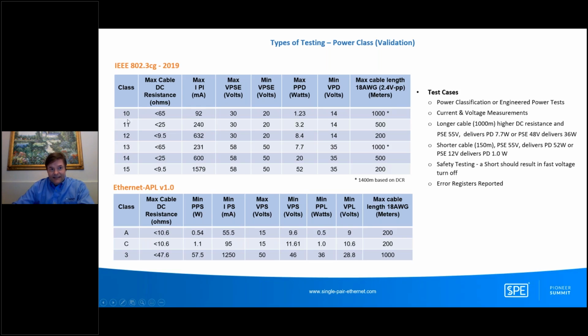But if we look at class 10 through 12 first, you'll see that the voltage power supply on the power source equipment is between 20 to 30 volts. So let's just say typically about 24 volts being supplied from the power source side. And you'll see then that we have maximum cable DC resistance. So we have high DC resistance, 65 ohms, 25 ohms, and 9.5 ohms. So this is a longer cable. And then for 24 volts, you put out 92 milliamps, and you can deliver 1.23 watts to the end device that's being powered. So that's relatively low power, and at the end device you have a minimum of 14 volts.